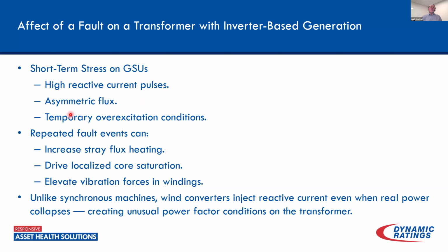The other thing is it could cause asymmetric flux within the core of the transformer, which is going to start to stress the transformer in different ways. There could also be temporary overexcitation conditions, due to frequency variations and over voltages, under voltages, as the inverters react to system conditions. When we see this, there can also be increased stray flux heating. It can drive localized core saturation, which can drive vibration and things like that, all of which are not good for the insulation in general. So that can also degrade the insulation.